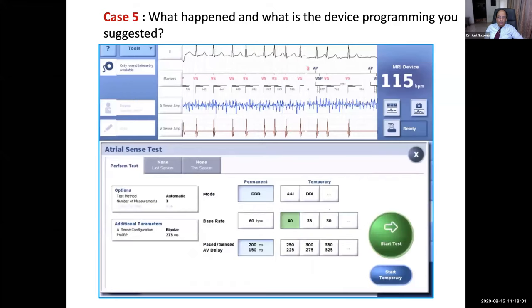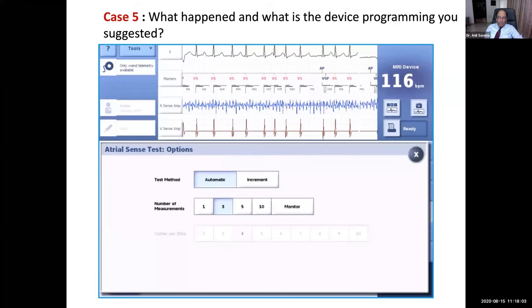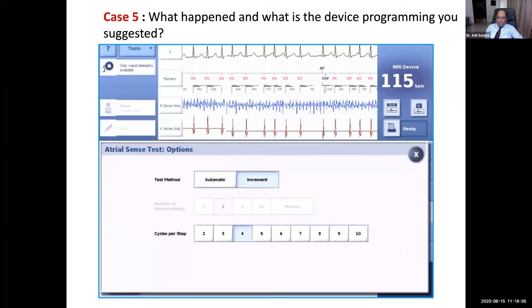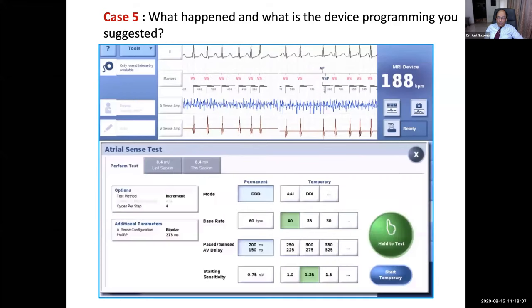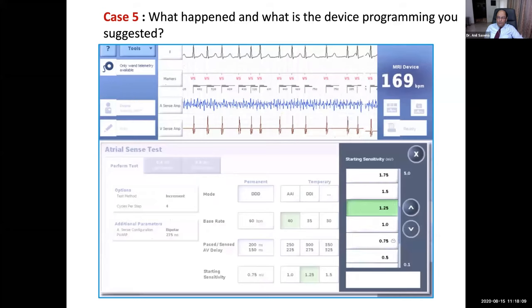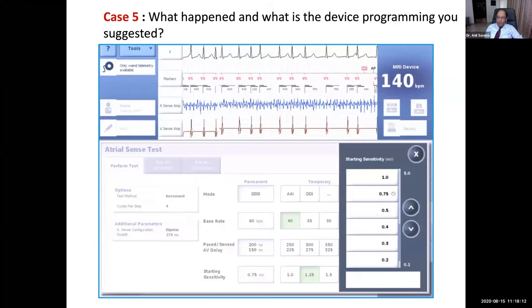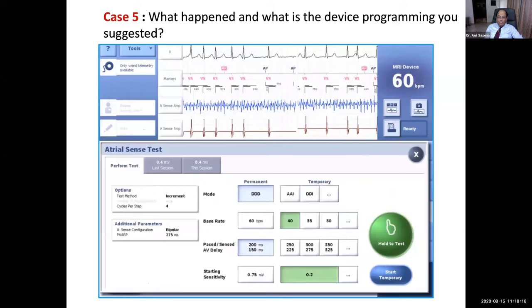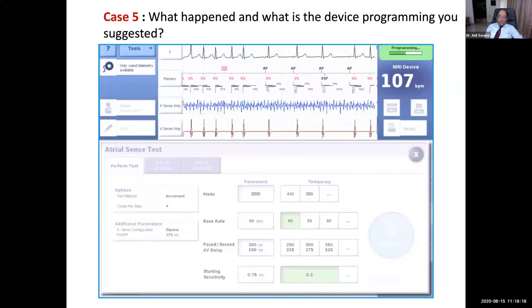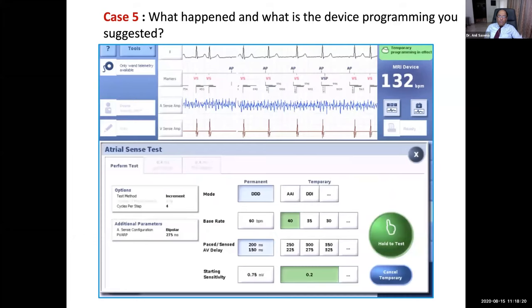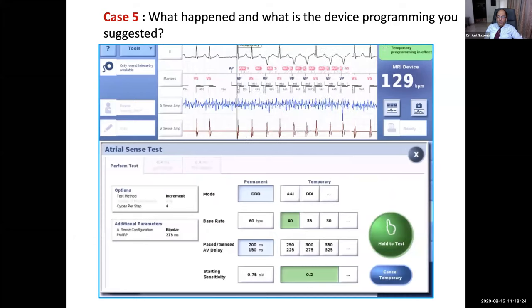We go to manual mode and change the sensitivity settings. We need to change it from the nominal 0.75 programmed down to 0.2, and start the test again in manual mode. Now you can see that it is sensing the AS, AR, that's how it should be all the time.